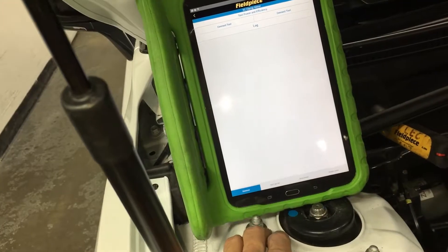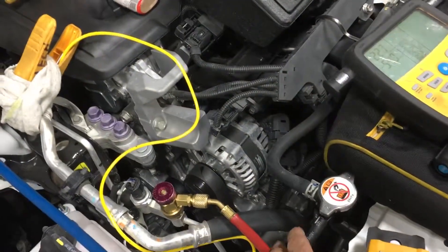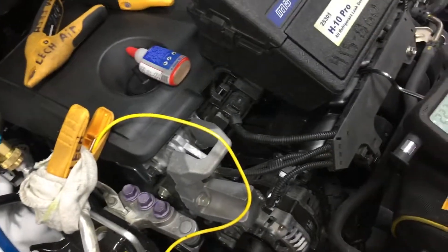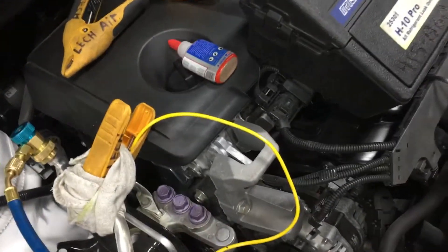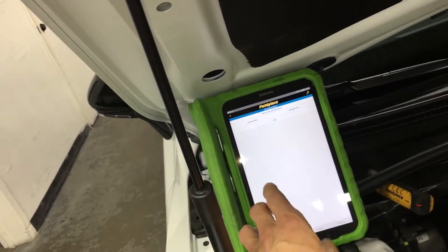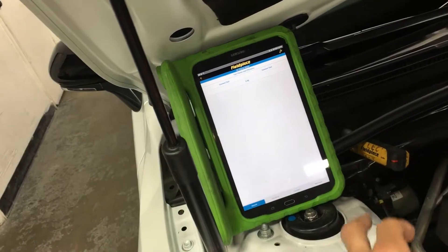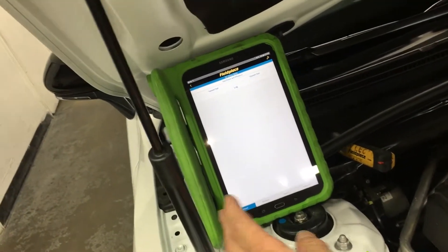You can also do your electrical monitoring. If you had a three-phase or two-phase compressor on here, you can wirelessly hook up and clamp on to the wires — it's hard to get to, but you can actually log your compressor watts. And when it's initially kicking in, you can get that surge wattage and tell when somebody overcharged it.